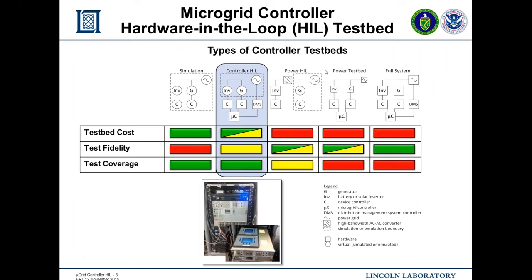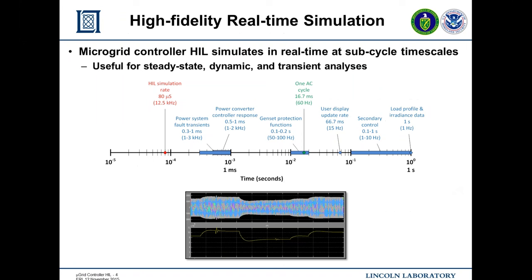We've been focusing on controller hardware-in-the-loop, covering tradeoffs in cost, fidelity, and test coverage. Fidelity refers to accuracy of tests — largely determined by whether actual control code from the final system is used. Test coverage means being able to test edge conditions without risking equipment damage. We see controller hardware-in-the-loop as the sweet spot for microgrid testing. Feedback from utilities confirms it's compelling because it enables steady-state analysis, dynamic and transient analysis, and takes controls behavior into account — something traditional power/distribution system tools cannot do.